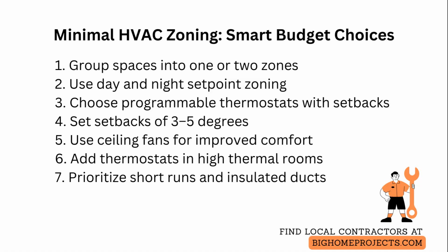Add local room thermostats only in areas with large thermal loads or irregular use, such as sunrooms, home offices, or finished basements, so you avoid overconditioning. When installing ducts, prioritize shorter runs and properly sized returns, and insulate exposed ducts to keep a simple system efficient.